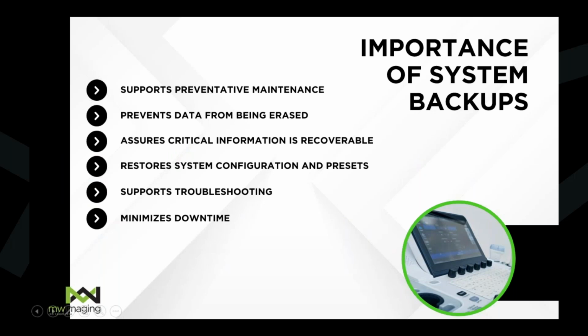It's important, obviously, if you have a good backup, you can prevent data from being lost. Some important data that sonographers would have on there would be the user information, measurements, workflow, annotations. All of these are saved when you create a backup for the ultrasound system. It assures that critical information is recoverable. You're able to restore system configuration and presets pretty quickly.